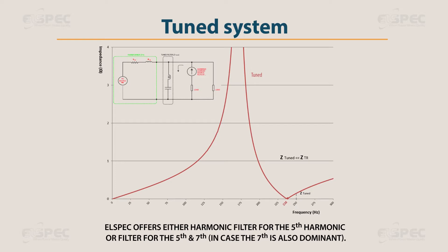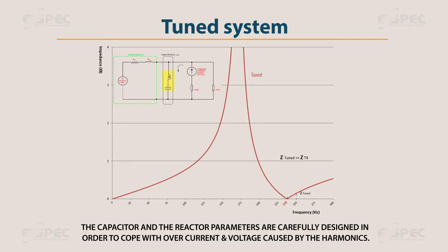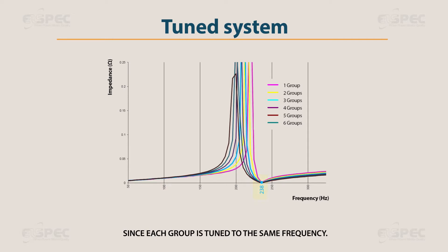Elspec offers either a harmonic filter for the 5th harmonic, or filters for both the 5th and 7th in case the 7th is also dominant. The capacitor and reactor parameters are carefully designed to cope with overcurrent and voltage caused by harmonics. The filter can be designed to absorb approximately 80% of the relevant harmonics. Regardless of how many groups are connected, the tuned frequency of the series resonance is always approximately 238 Hz, since each group is tuned to the same frequency.